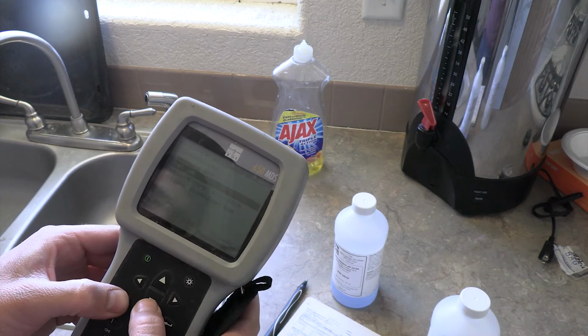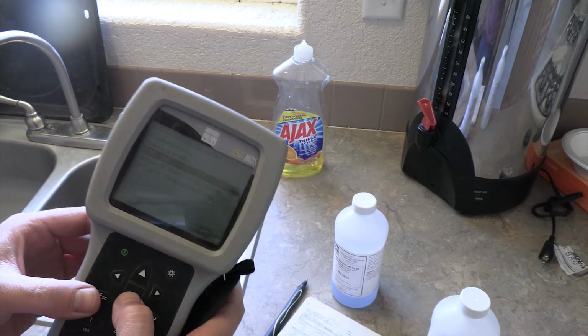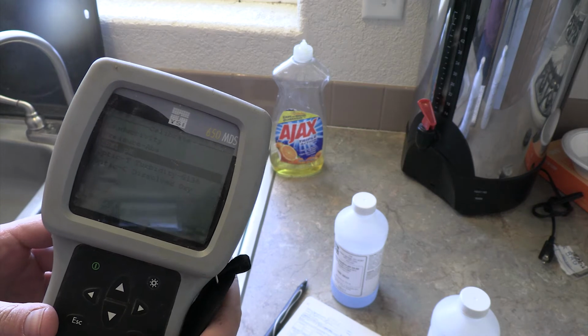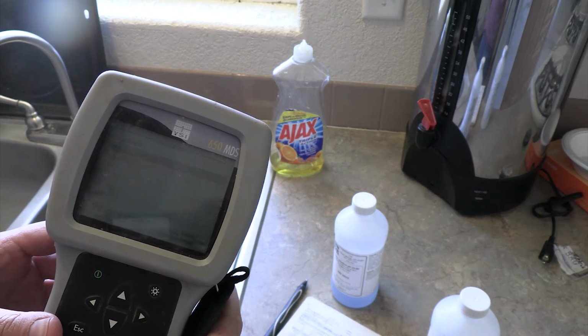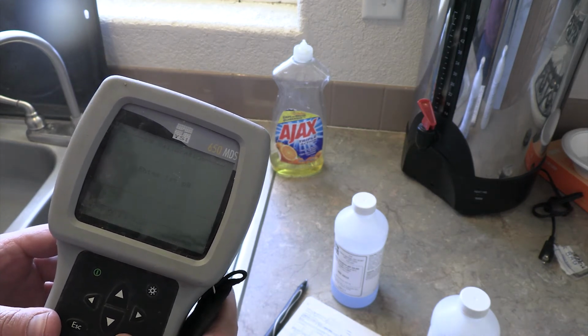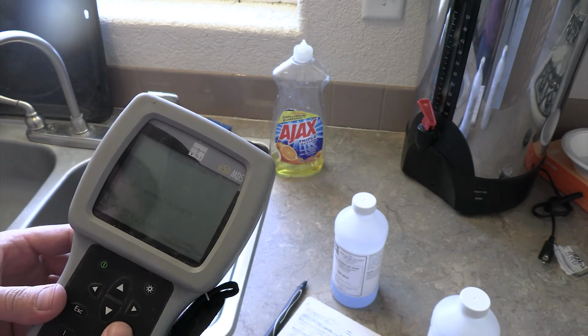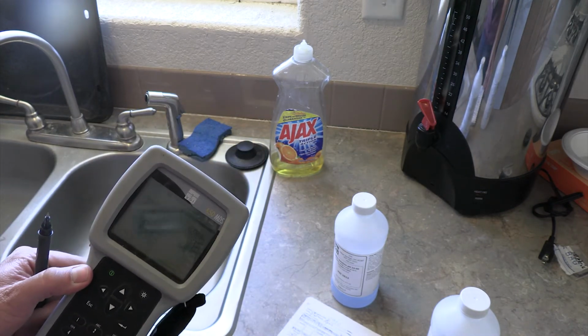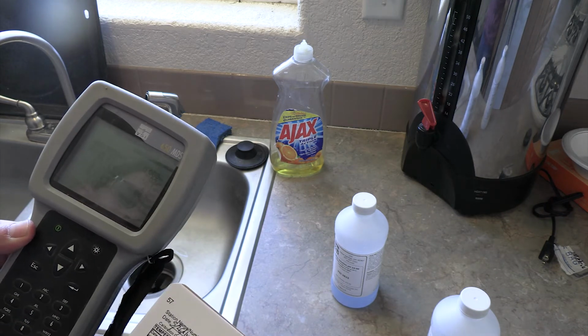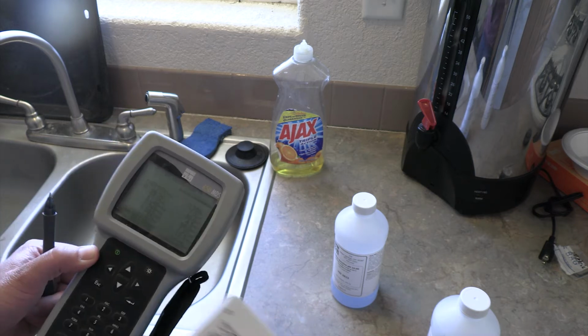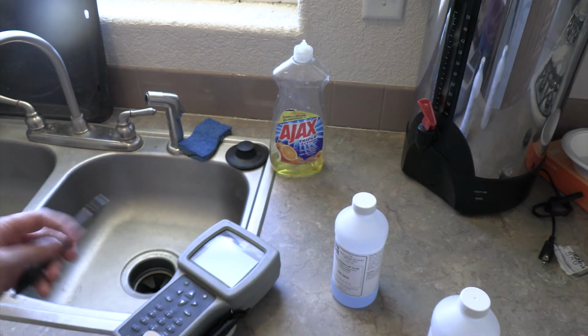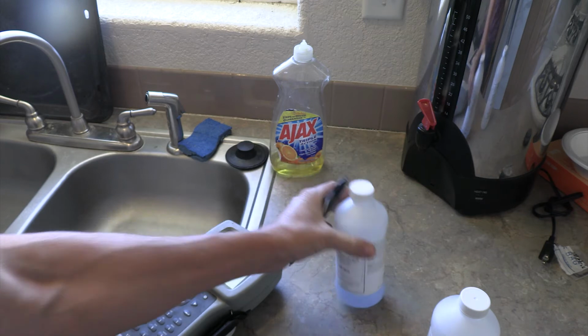Let's go back over here. When we're back at the calibration screen, you go down to pH, the third one down, pH 2-point calibration. This is 7. Let's just use 7 so that we can get the temperature, and once we get the temperature, we can go back and recalibrate. Both of them should be about the same temperature, considering they've been sitting in the same space. So, 25, which is great because we don't need to change it. As long as it's about 25, I think it's like 23 and up.